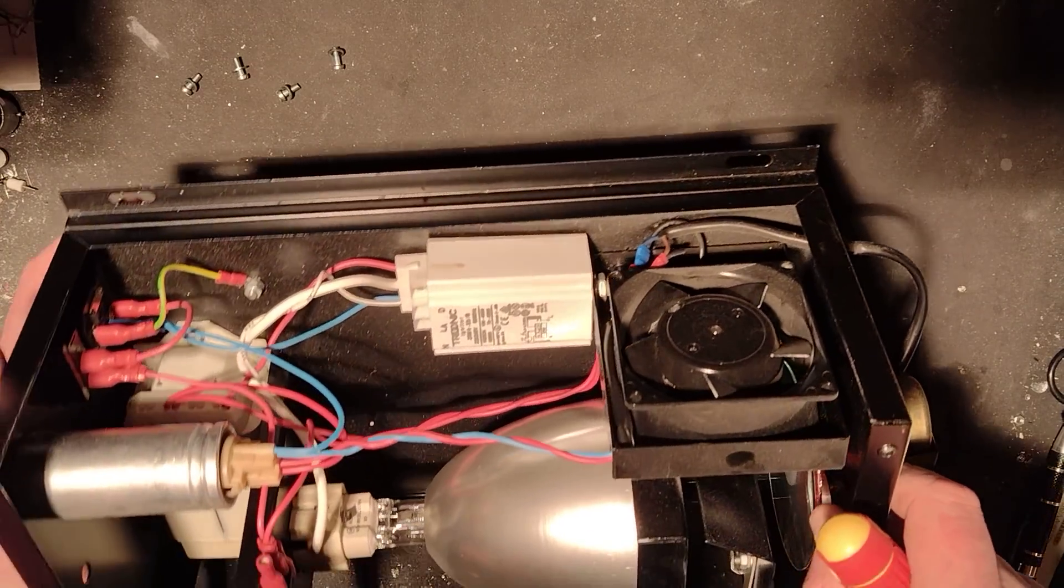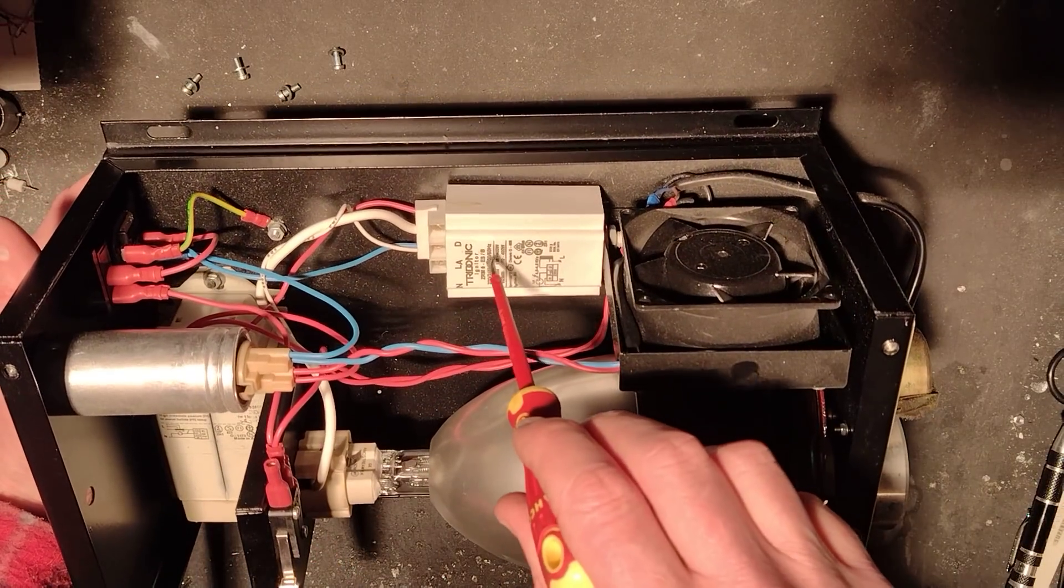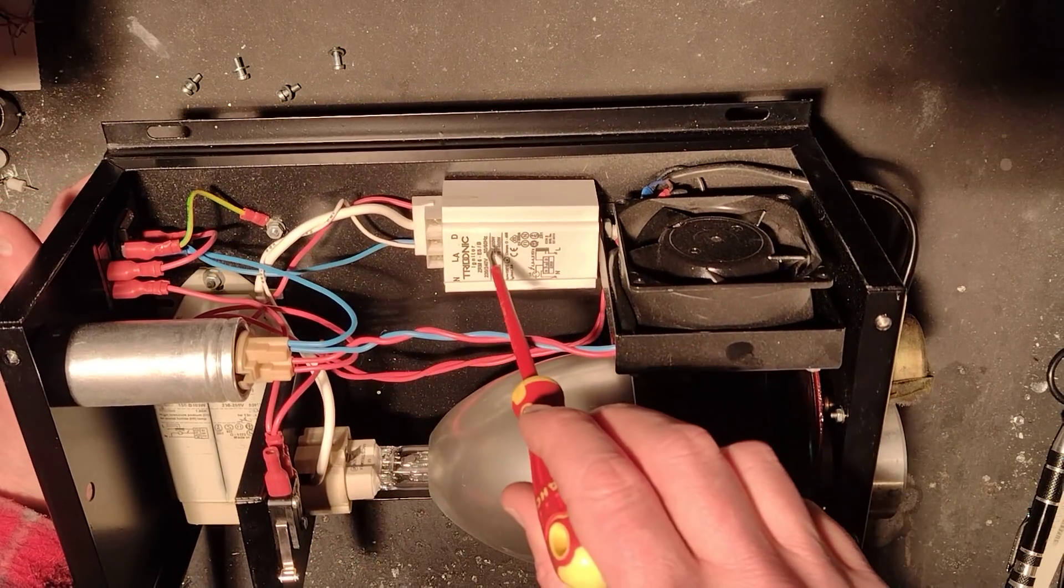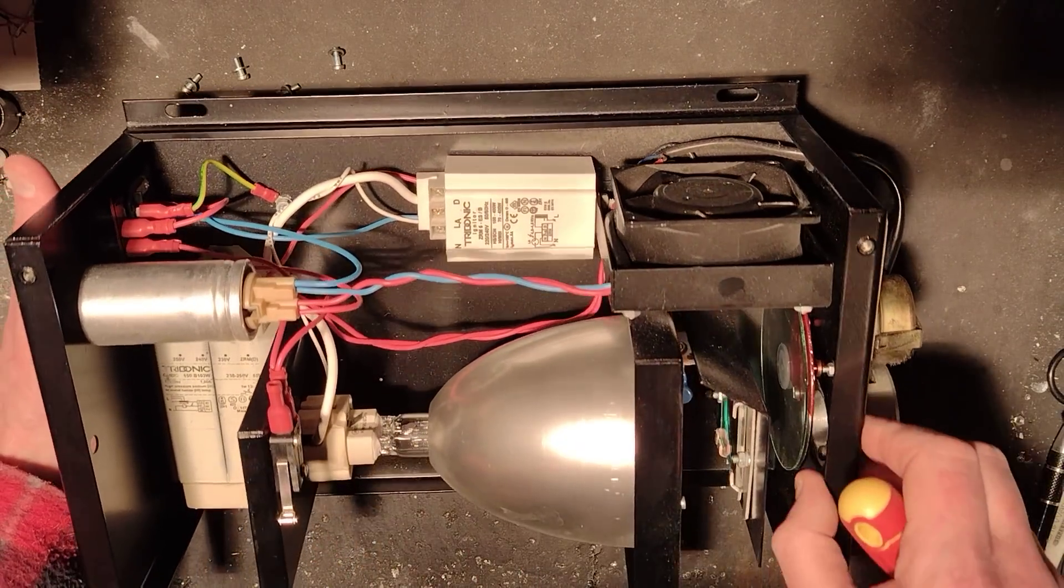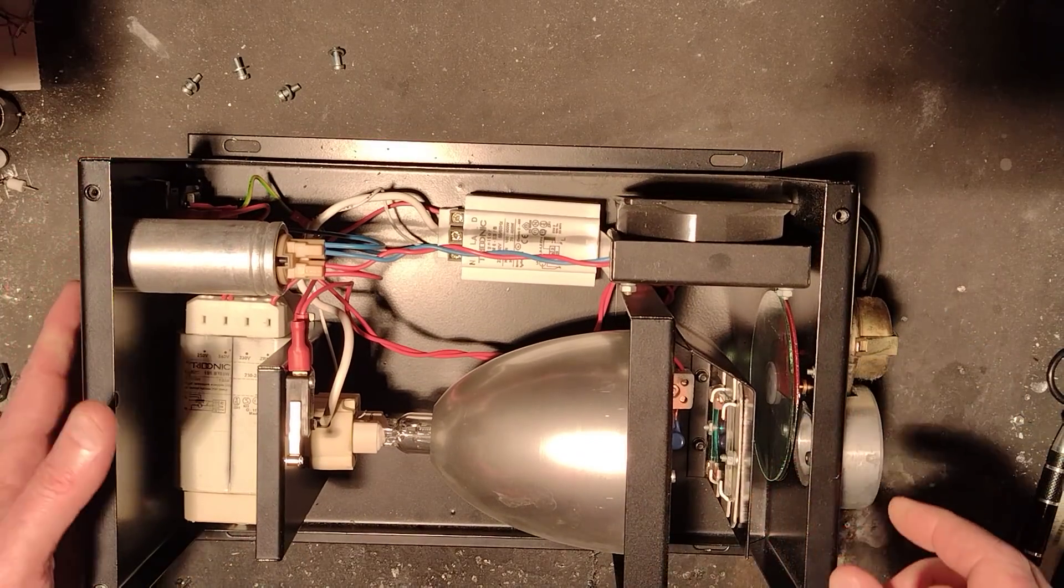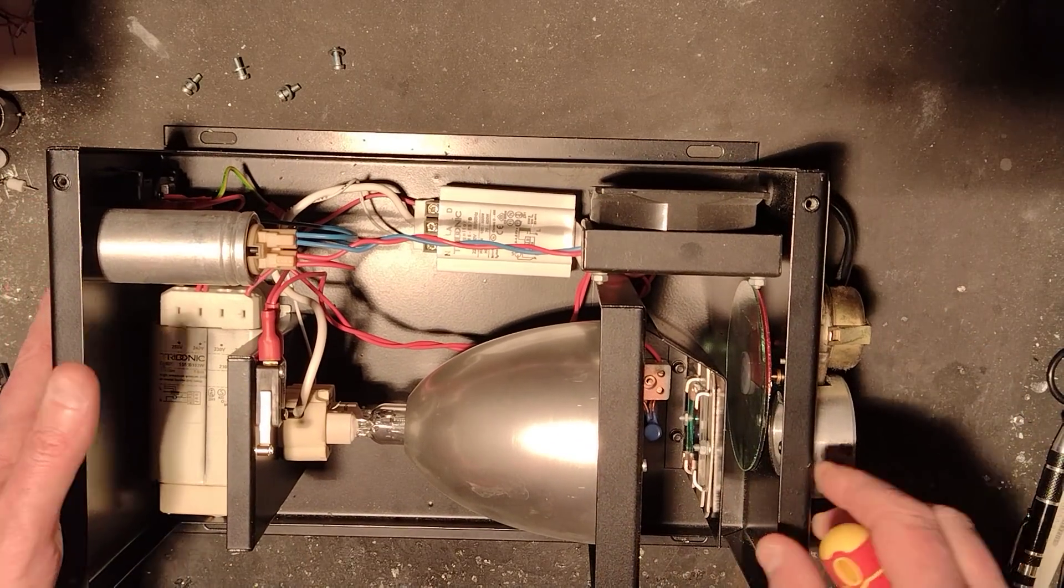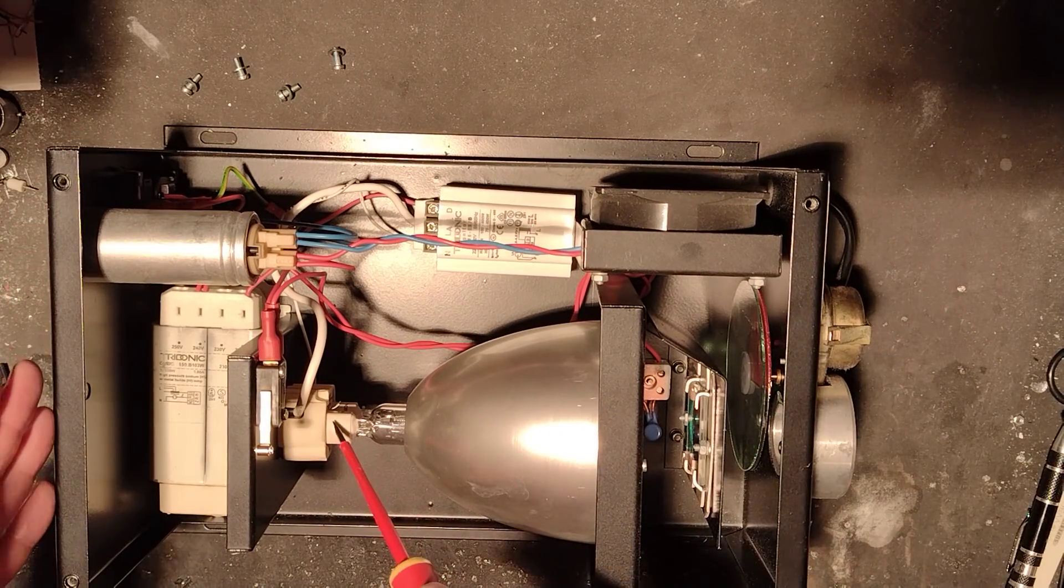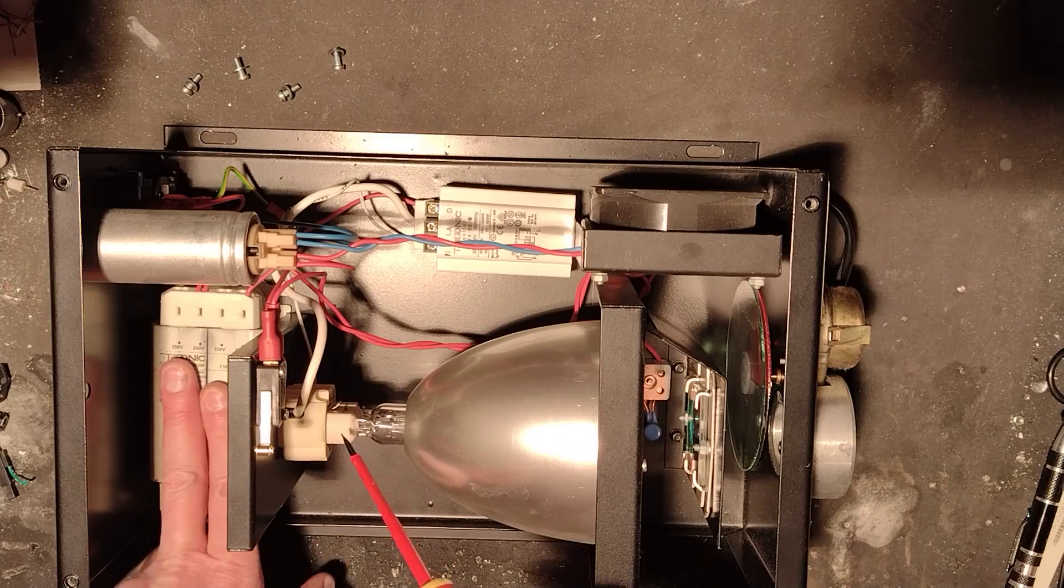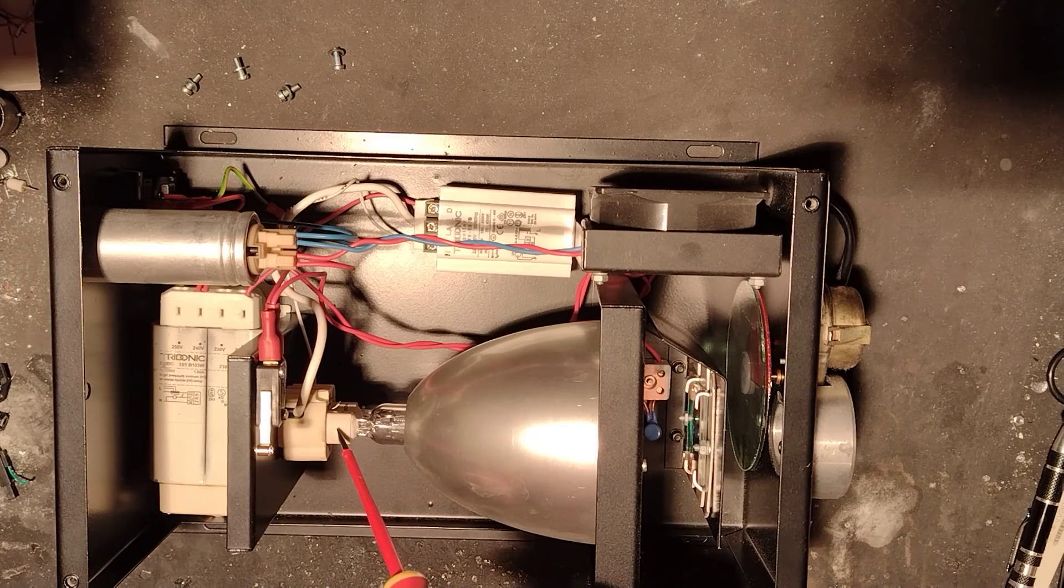So in operation, when power is applied to the ballast, the ballast output goes to this device here, which is an igniter. The igniter superimposes a 4000 volt pulse onto the output from this current limited supply to the metal halide lamp in here.